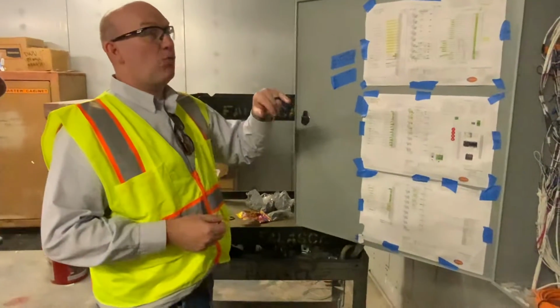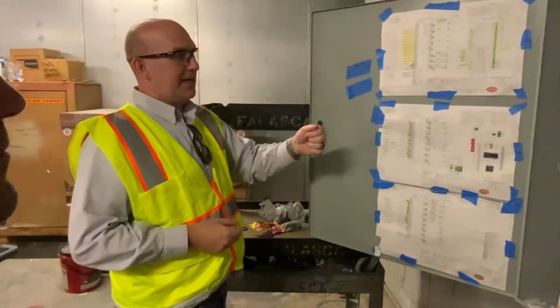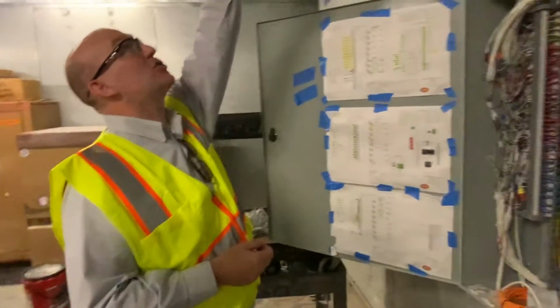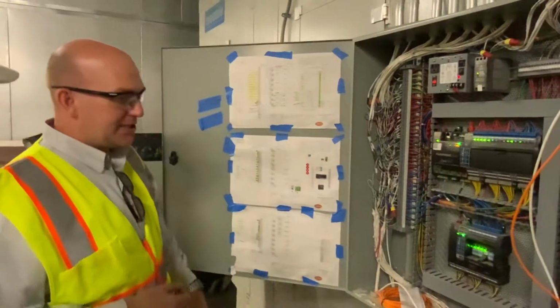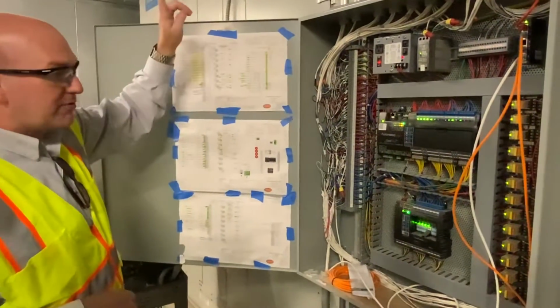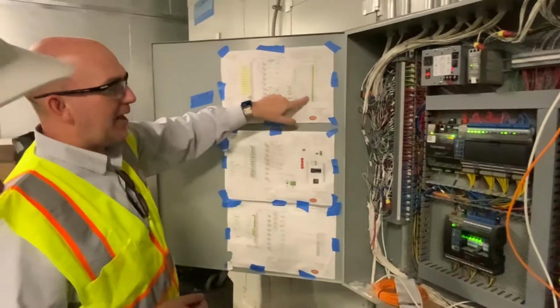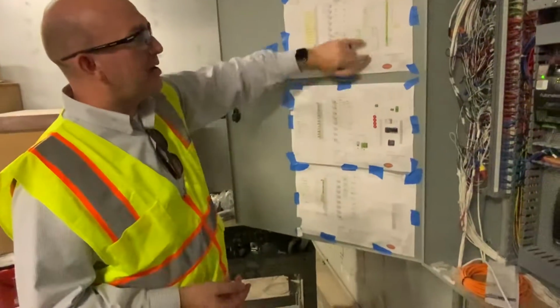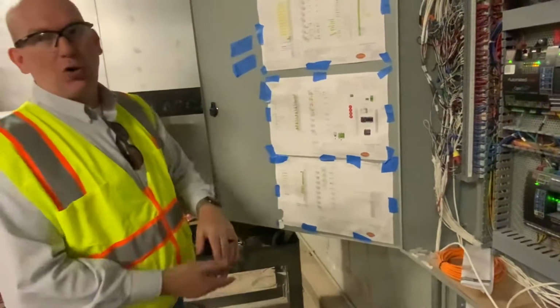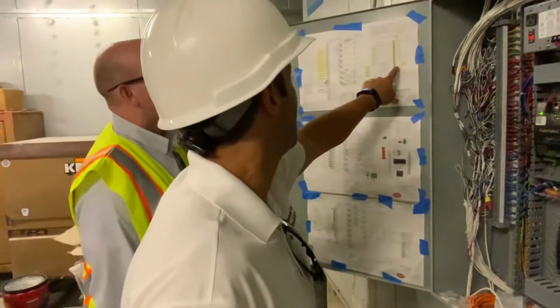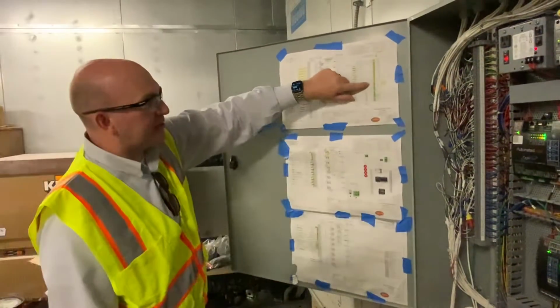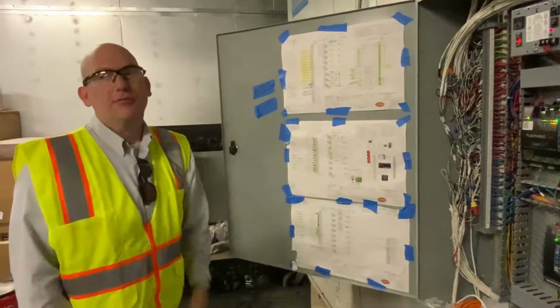And it's set up so that if both VFDs go out on the exhaust, the unit shuts down and the damper's closed. If one of them's running, the unit can run. Same on the supply. One fan's running, the unit can continue to run. But if both of them drop out, the whole unit shuts down. Okay, so electrically they're tied together. Correct. You got it. So you see that the supply and the exhaust are tied together. That's how. That's it. All right. Make sense? Yes. Thank you. Yeah, no problem.